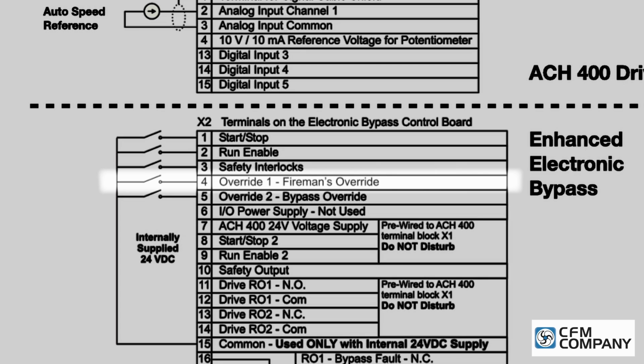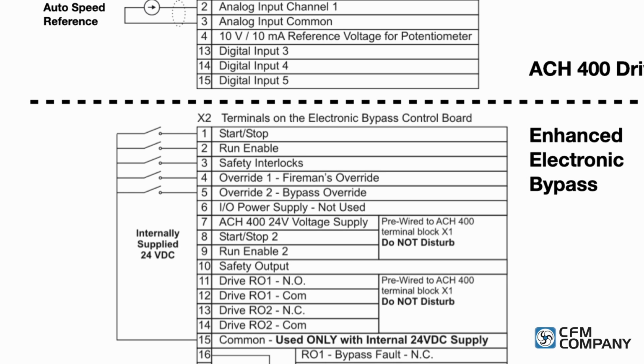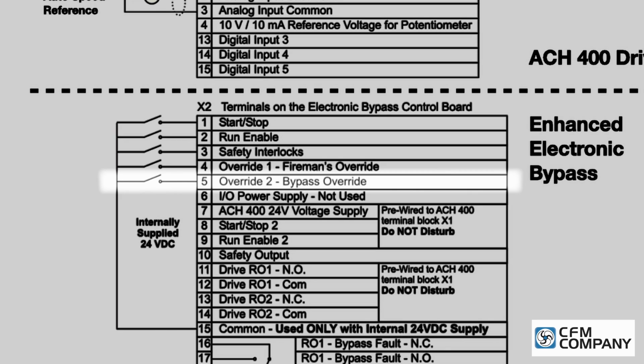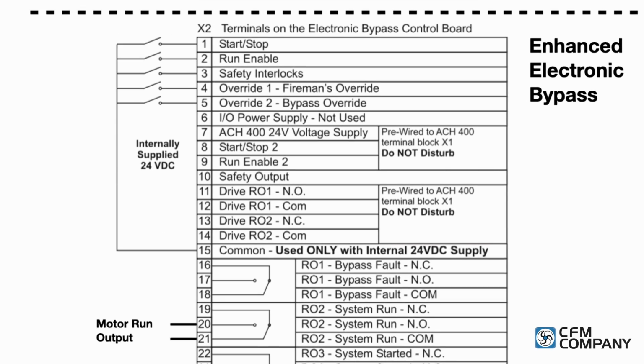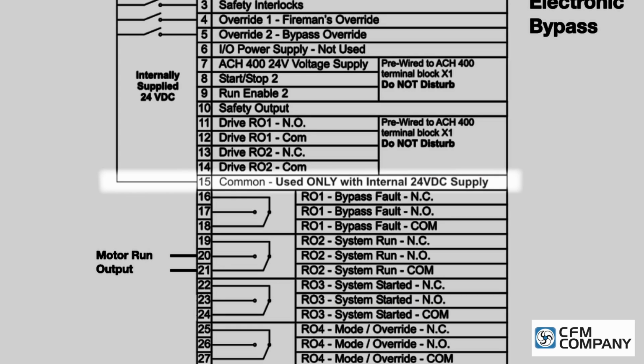Terminal 4 activates the fireman's override. This input forces the bypass to run the motor at 100% speed across the line, ignoring all safeties, faults, and user inputs. Fireman's override mode is designed to run to destruction. Terminal 5 activates the bypass override. In this mode, the bypass follows the start-stop, run-enable, safety interlocks to run the motor in bypass. Terminal 15 is the common reference for the bypass digital inputs.